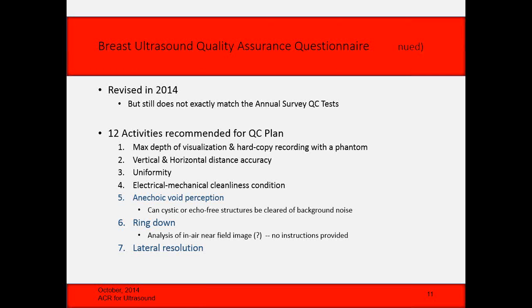Make sure you're adhering to universal infection control procedures. And this is interesting. They have a separate thing on the QA plan about cleaning transducers. This is one you cannot check, we don't do. You can't opt out of this one, by the way. There isn't that checkbox. So, and thank goodness. But daily is actually the minimum frequency that can be selected. And of course, it should be done after every patient, especially these days, right? So hopefully that is being done all the time. So this is just to say, yes, that's being done regularly because the system was clean when I checked it.